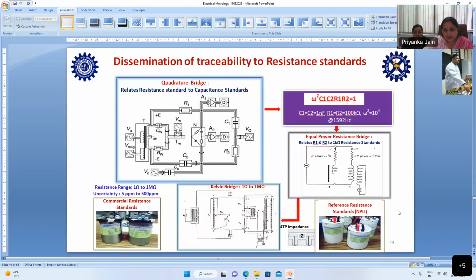Now here is a summary of how we are defining the resistance standard at NPL. The quadrature bridge interrelates the capacitance with R1, R2. R1, R2 are the 100 kilo ohm resistance standard. Here you can see our balance condition. Now the 100 kilo ohm resistance standard is compared with a 1 kilo ohm resistance through an equal power bridge. Equal power means that the current in one arm is I, and in the other arm the current is maintained at I by N. So if your resistance is 100, then the I square R will be equal if your current is 1 by 10th of this current.